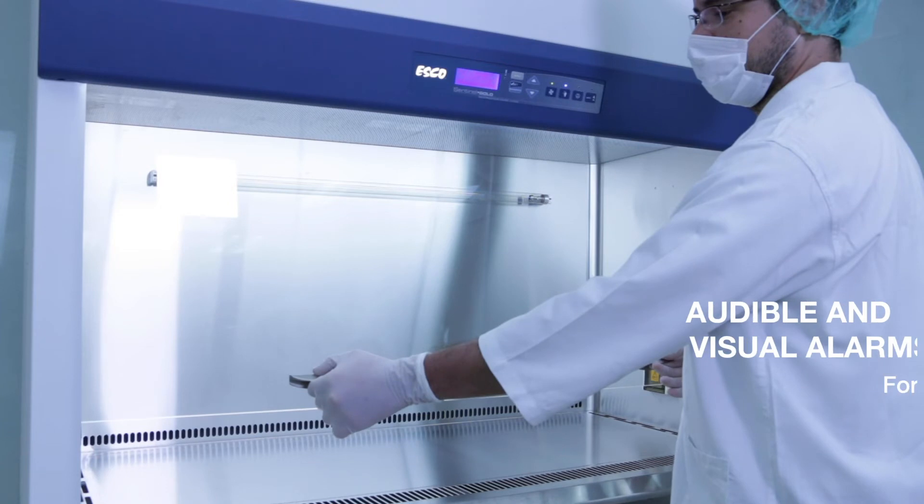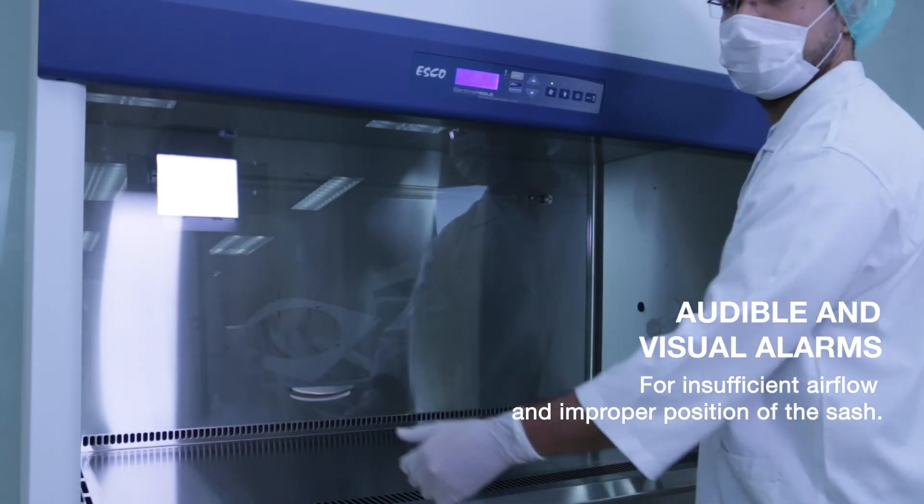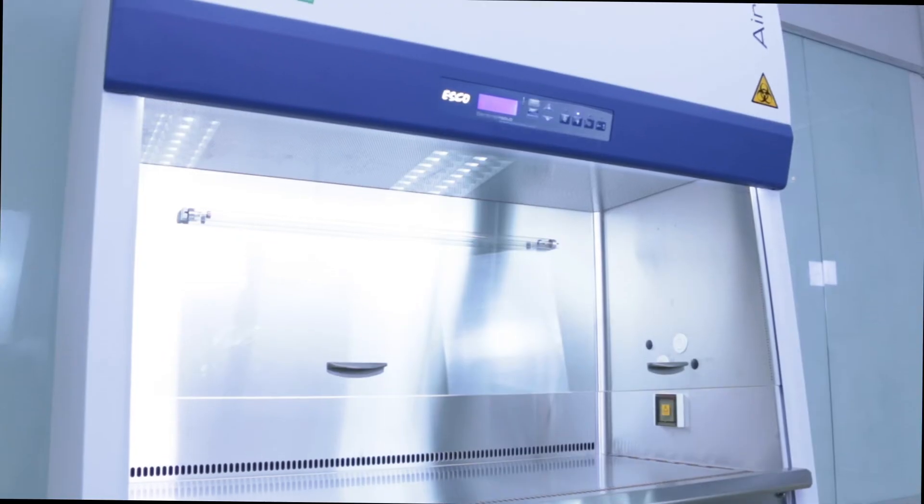There are audible and visual alarms in cases of insufficient airflow and improper position of the sash.